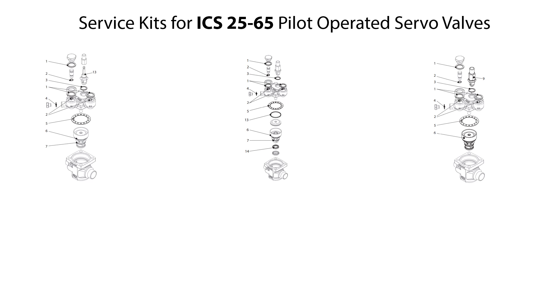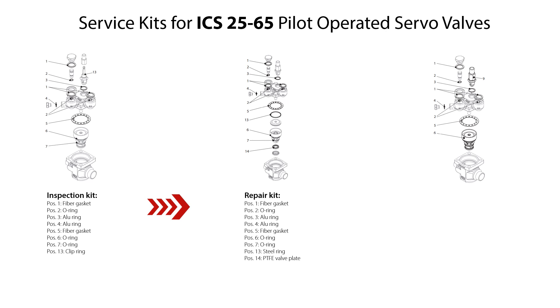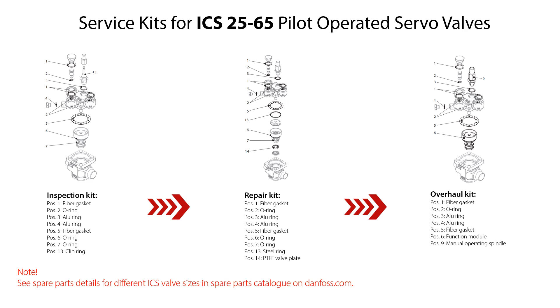You can use different available service kits to replace worn valve parts during reassembly of the ICS 25-65 pilot operated servo valves. The available service kits include: an inspection kit which includes fiber gaskets, o-rings, alu rings and clip ring; a repair kit which includes fiber gaskets, o-rings, alu rings, steel ring and PTFE valve plate; and an overhaul kit which includes fiber gaskets, o-rings, alu rings, function module and manual operating spindle. Please look for spare parts details for the different ICS valve sizes in the spare parts catalog available on danfoss.com.